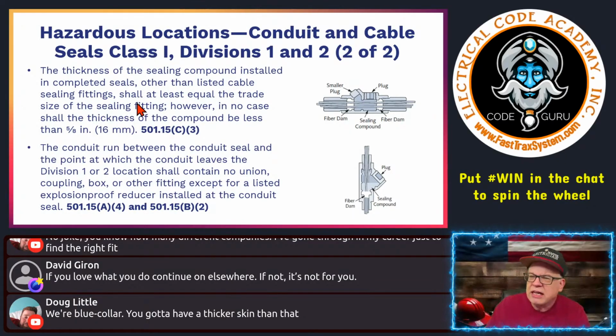All right, so here's what it says. It shall be at least equal to the trade size of the sealing fitting - other than listed cable sealing fittings. However, in no case shall the thickness of the compound be less than 5/8 of an inch.